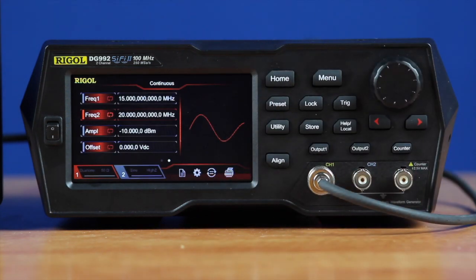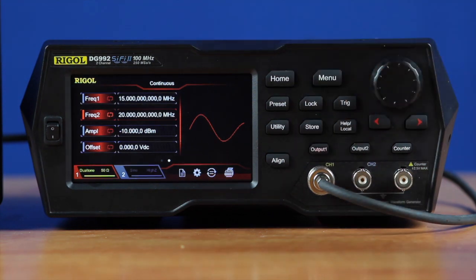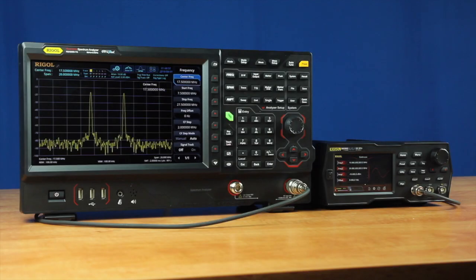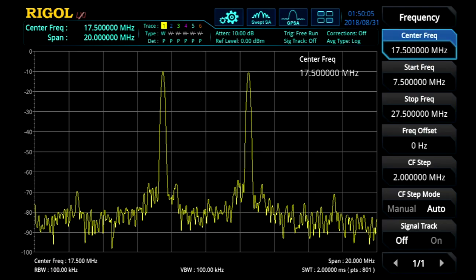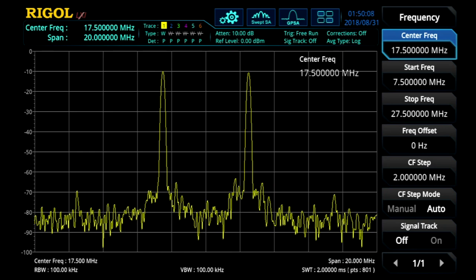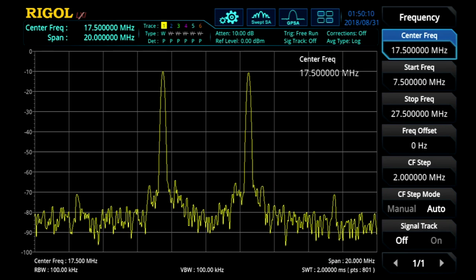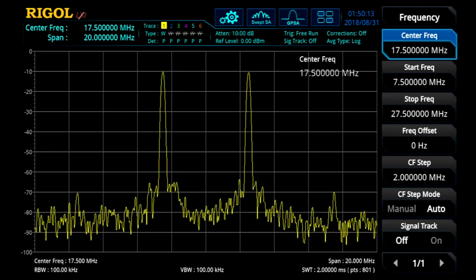I've already got the amplitude set up to negative 10 dBm, but I can set it to other forms of amplitude, and I can also choose an offset. Then I'm going to turn the output on, and in order to show the dual-tone functionality of this waveform generator, I've actually connected it to a spectrum analyzer, so we can see the two different frequency tones on the display, centered around the 17.5 megahertz center frequency.